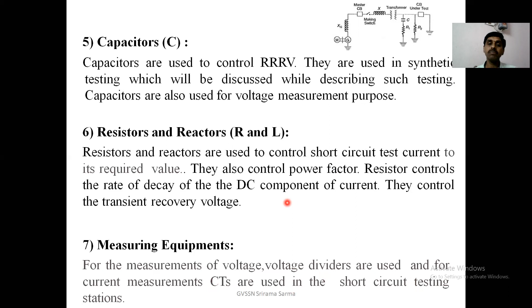Now the testing procedure. During a short circuit test, several switching operations are performed in sequence in a very short time. For example, if you see this circuit, what is the sequence of operations here? After running the driving motor of the short circuit generator to a certain speed, this motor is switched off. Then the impulse excitation is switched on. Then the master circuit breaker is closed and the oscillogram is switched on for measurement purposes. Then the making switch is closed. Then the circuit breaker under test is opened. That means when the short circuit current is applied, this breaker is opened to test its interrupting capacity.